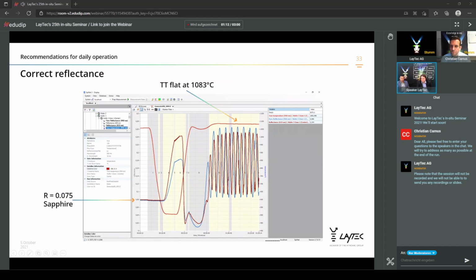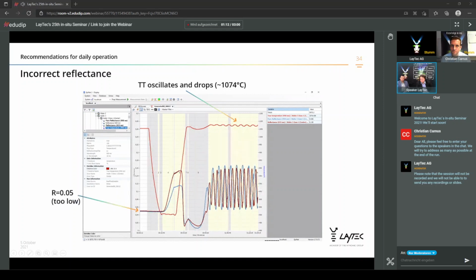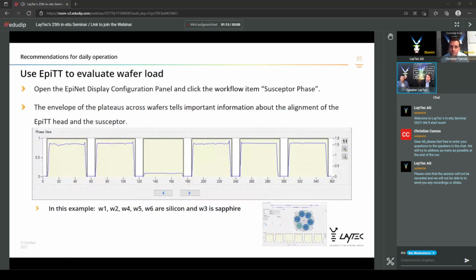straight temperature line without any oscillations. If we do that with the wrong value, in that example it is set to 5%, even this minor change of the reflection will already cause some residual oscillations. So it gets very difficult to determine the real temperature value.